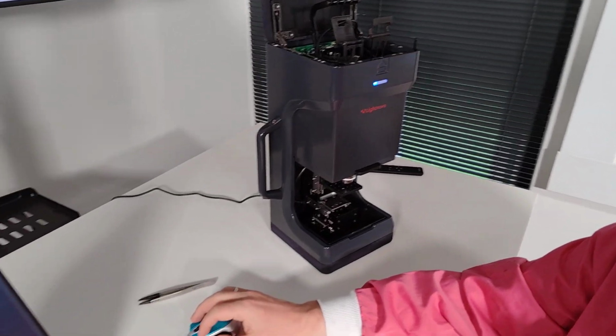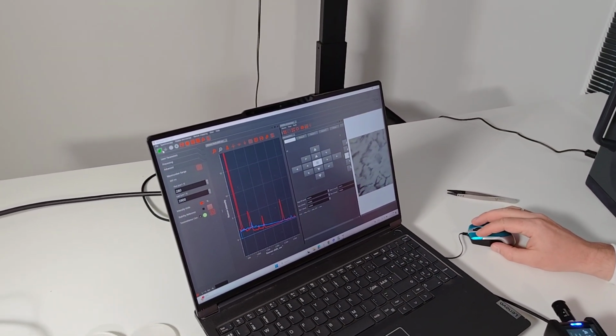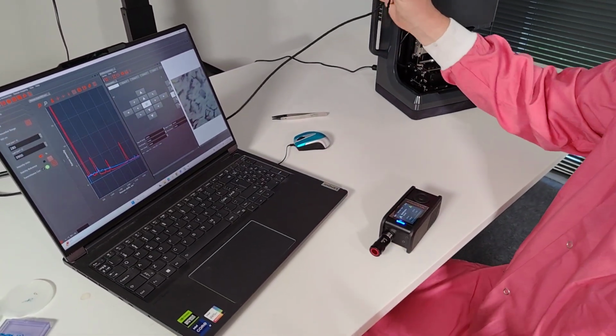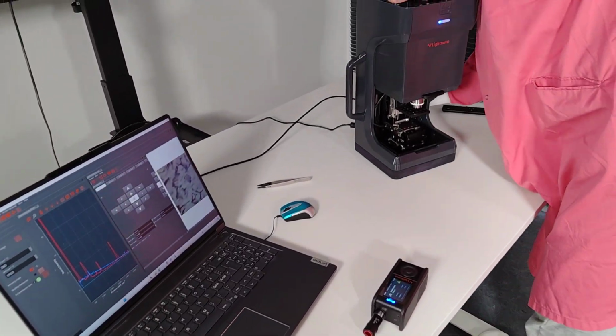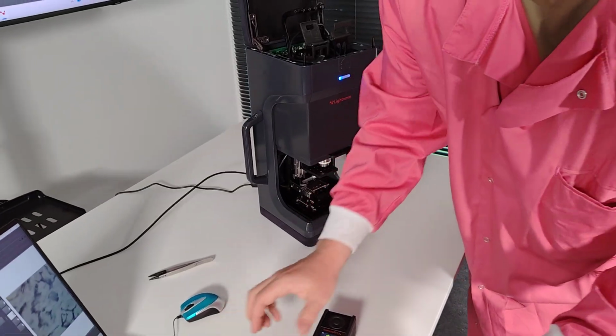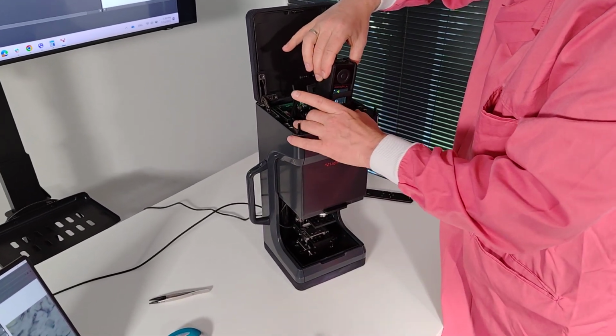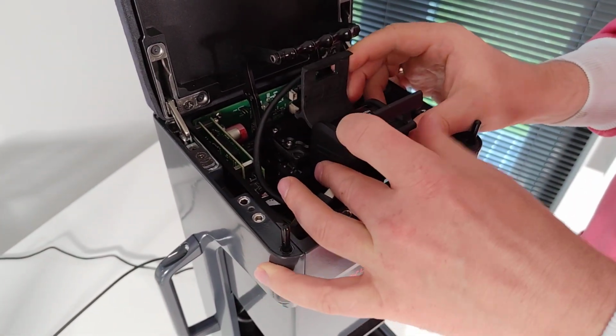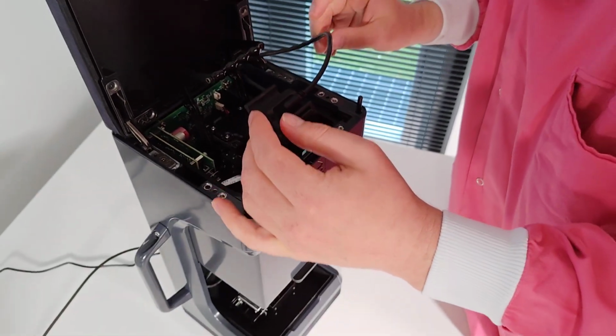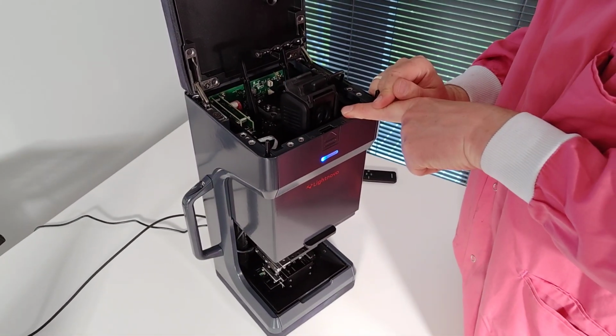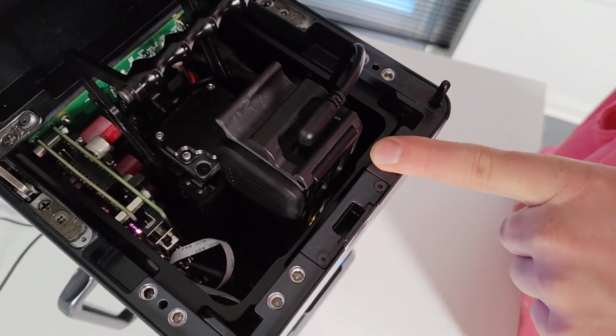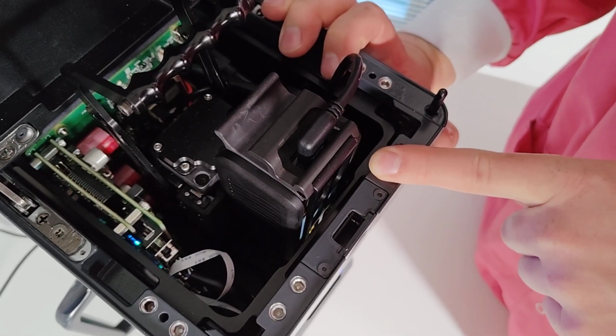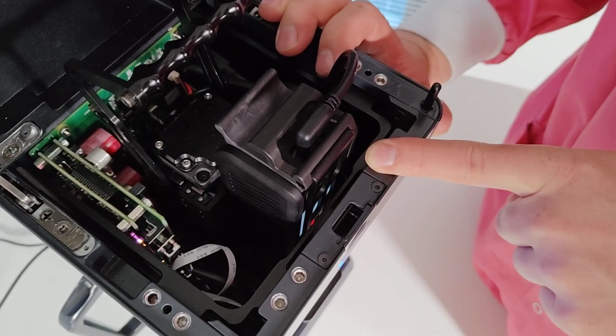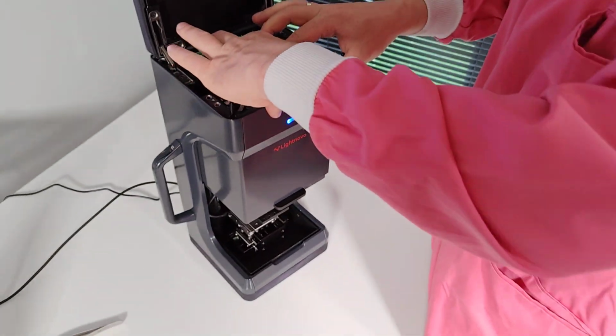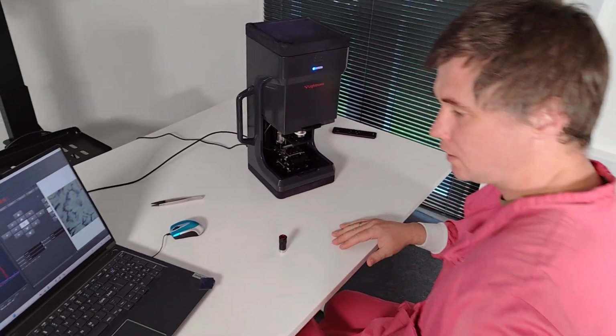And first of all, we should of course connect it to the microscope. So let me do that. Instead of connecting it to the miniRaman, I would place the USB to the back of the spectrometer. Next step, I disconnect the probe and I put miniRaman inside the microscope. One, two, connect. Yes, it's connected and it's loading now. So we should wait until the miniRaman inside is blinking blue, which means it's ready to be connected, and it's yellow. We wait a second. Red, blue, good. And you hear it by the sound on the PC. So now we can close the cover and here press connect.